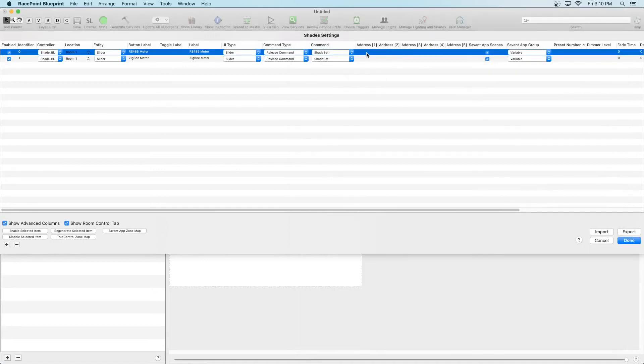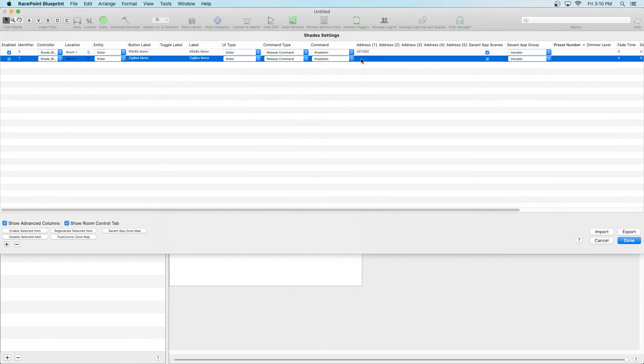In this scenario, the two shades we added were the ST50AC1 shade, which has an Integration ID of 001002, and this Zigbee Shade1, which has an Integration ID of 00100C. Take those Integration IDs and add them to the respective shades under the Address section.